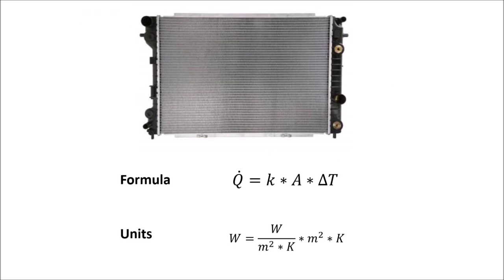But to make this formula more usable in daily engineering life, there are two simplifications. The area is not the complete surface area of the radiator, but only height times width—in other words, the radiator net area. That's easy to measure in every workshop, and different depths will be compensated by a higher or lower k factor.